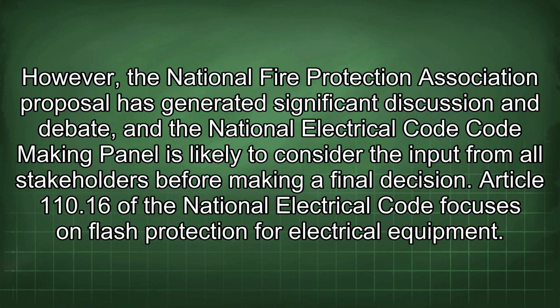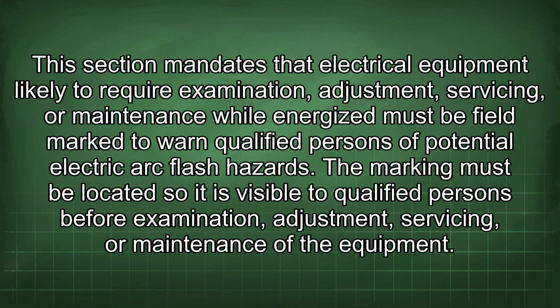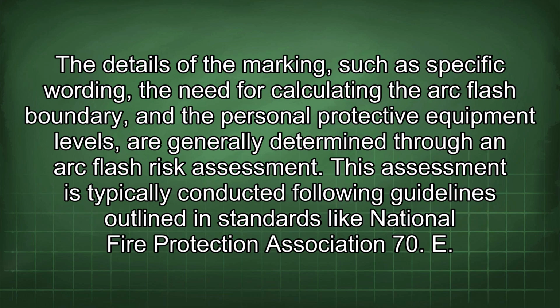Article 110.16 of the National Electrical Code focuses on flash protection for electrical equipment. This section mandates that electrical equipment likely to require examination, adjustment, servicing, or maintenance while energized must be field marked to warn qualified persons of potential electric arc flash hazards. The marking must be located so it is visible to qualified persons before examination, adjustment, servicing, or maintenance of the equipment. The details of the marking, such as specific wording, the need for calculating the arc flash boundary, and the personal protective equipment levels, are generally determined through an arc flash risk assessment.